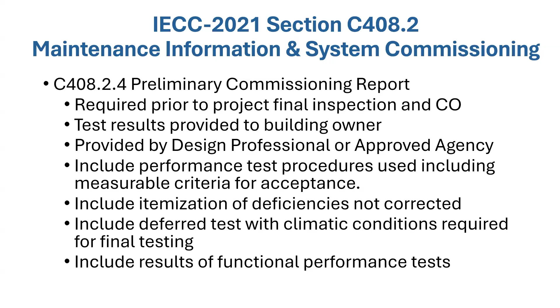If you have to test a boiler in the middle of July, that's a problem. And if you're testing a chiller in January, or a cooling tower, that's also a problem. So you have a preliminary report. Once the building is essentially complete, you test all of that and make up a list of what wasn't tested or what needs to be adjusted or changed to make everything work. All of that has to be itemized so the contractor and everybody knows what they need to do, and the owner knows what still needs to be done. That's the functional performance testing.